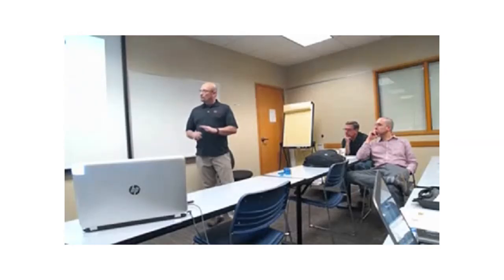Okay, so you guys use your digital multimeters, which is good, and you have a Megger, and like I said, the tester we're talking about has all that built into it, as well as high pot testing. And so what we do, just real quick with that, is we're testing just like what you would do with your Megger. On a 480 volt motor, we're doing a 500 volt megohm test, 60 seconds long. And we do the lead-to-lead resistance test, we do the megohm test. If all that looks good, then we start doing these other tests here, the high pot test and a surge test.